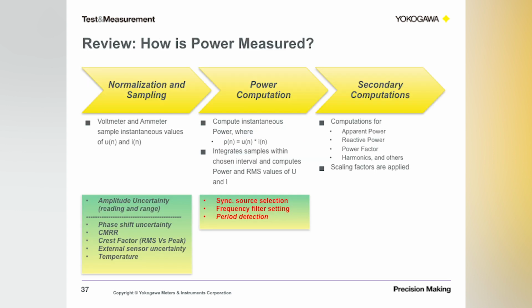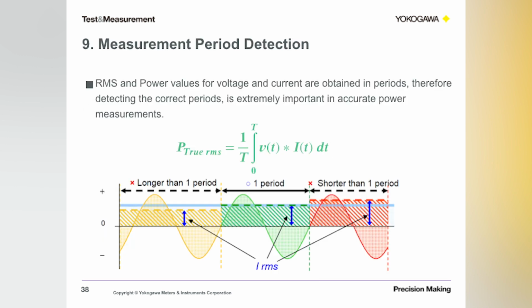So now, we have discussed many of the factors that can affect the uncertainty on the front end side. The A to Ds, the gain circuits, all that stuff. So let's talk a little bit about the factors that could affect your measurement on the computation side of things, right? So let's focus on the sync source, the frequency filter setting, and the period detection, right? When it comes to accurate power measurements, the biggest one is the ability of the device to detect the period of the measurement, right? As RMS and power values for voltage and current are obtained in periods, detecting the period in power measurement is extremely important.